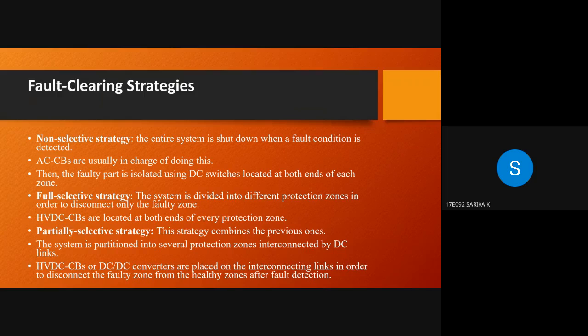Partially selective strategy. This strategy combines the previous ones, that is, both the non-selective strategy and full selective strategy. The system is partitioned into several protection zones interconnected by DC links. HVDC circuit breakers or DC to DC converters are placed on the interconnecting links in order to disconnect the faulty zone from the healthy zones after the fault detection.